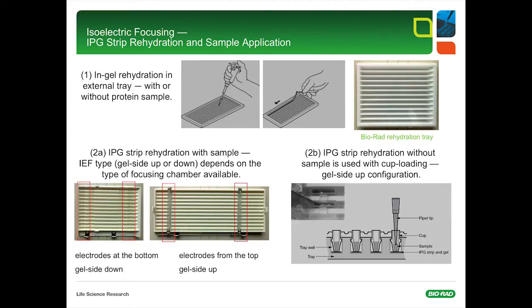IPG strips rehydrated with sample can be run in two different configurations, gel side up or gel side down, depending on which focusing trays are available. Highly recommended is gel side up focusing. This strategy usually leads to better and more reproducible results. If IPG strips are rehydrated without sample, then sample application is done with sample cups placed on the gel of the IPG strip, usually on the acidic side. Sample cups offer an alternative method of sample loading and can often improve resolution, especially at extreme pH ranges and for hydrophobic proteins.